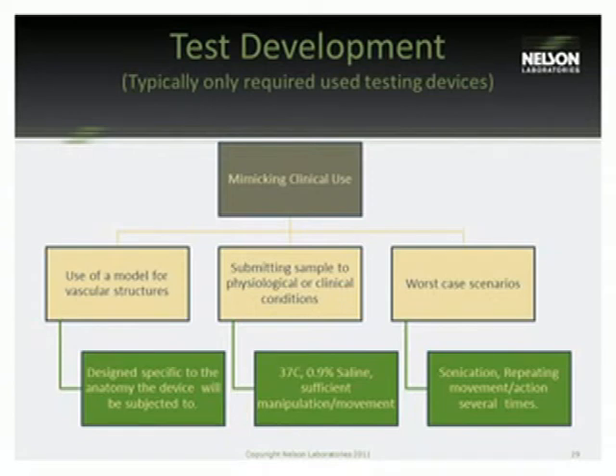Subjecting samples to physiological or clinical conditions as far as temperature, saline, and also sufficient manipulation or movement that may take place clinically by the physician during use of the product. Worst case scenarios are also a good idea. Speaking of sufficient manipulation and movement, in many cases we will reuse essentially the device, or not so much reuse, but retract it in advance, say if it's an introducer, a catheter, a guide wire, something of that nature, several times to mimic if the physician were struggling to get that product in the right position in the vasculature. But also sonication is another addition to worst case scenarios. That's above and beyond what we normally do for extraction, but that will definitely remove pretty much all particulate matter off of a device. So that's another option for a worst case scenario.